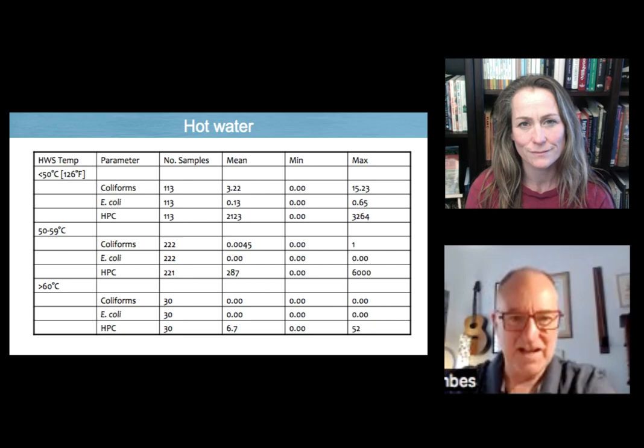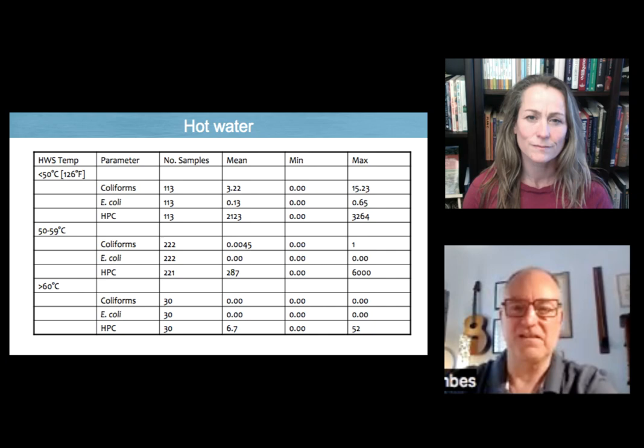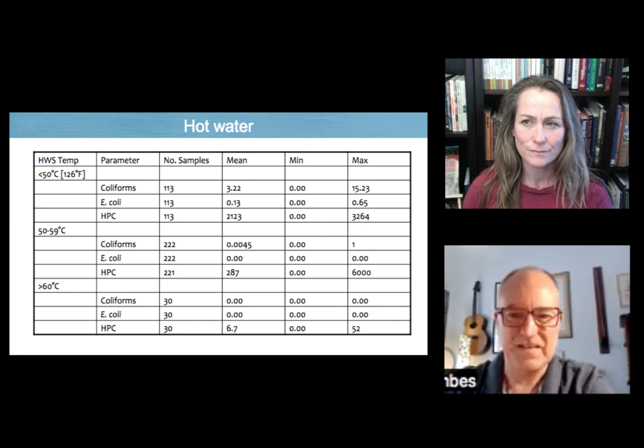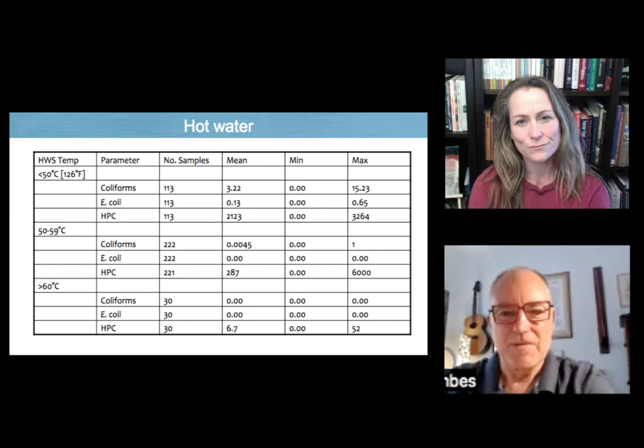But above 60 degrees, you can actually see there's an absolute elimination of coliforms and E. coli. And there's almost none of the heterotrophic plate counts left in water. So just note that your mains water supply will have heterotrophic plate counts in it because that's all bacteria and you need bacteria in water. But the indicators of pathogens E. coli and coliforms are completely reduced.